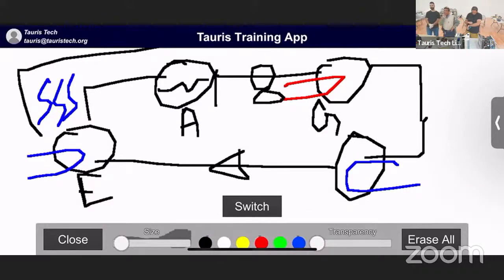The old style was ammonia absorption, where you had aqua ammonia, which is water mixed with ammonia. The new systems are called lithium bromide. Now, the difference with an ammonia absorption system and a lithium bromide system, ammonia operates above atmospheric pressure. So it's like 200, 300 PSI. In a lithium bromide system, I mentioned something earlier, I'm not sure if you guys remember. I said if you boil water at 40 degrees and then you have steam at 41, is that superheated? So in this machine, water is the refrigerant, right?